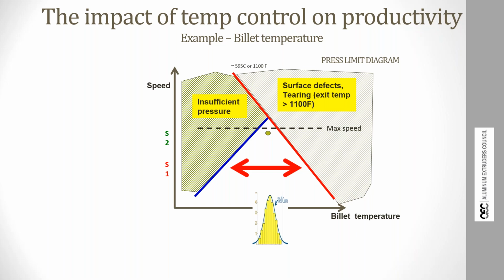So if you've got 3 zones with 6 thermocouples, or 4 zones with 8 thermocouples, you don't want a degree of variance in angle cut as well as a quarter-inch difference — you could have one touching and one not even touching. I've seen it, I've got pictures I've shared in other press maintenance sessions where one's long and one's short: one gets pushed all the way back and buries in, making a dent, like you and I standing beside each other. But anyway, consistency is what matters.